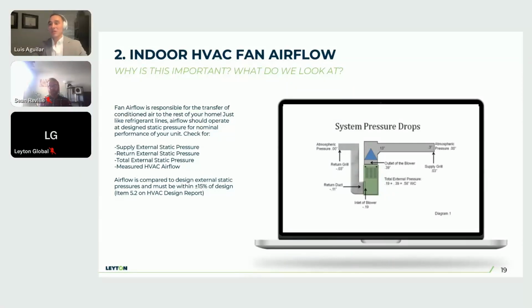There's airflow going throughout your home, and that's good, right? Because that means your home is being conditioned, your set points are being met, or set point in this case, depending on how many zones you have. And so that's another thing that Energy Star prioritizes in the checklist, and we will take some measurements to do so. And so in addition to doing that, by getting the external static pressure and using the manufacturer data that they provide to us, we can calculate the airflow currently when we do the testing of the unit and see if that's on par with, once again, what the scheduled airflow is. And so we want to make sure it's within plus minus 15% of the design airflow. And if that requirement is met, then things are looking good, and we check that off and move to the next thing.